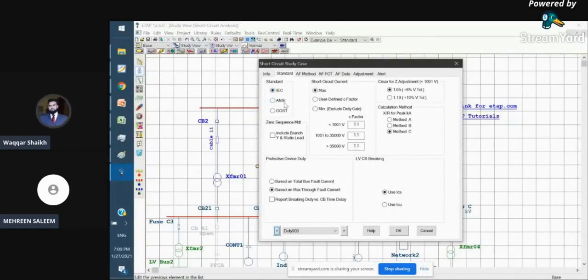There are many options here which will be required from you to select in order to run the simulation. For example, if you are selecting maximum short circuit values, it will give a different set of results. These maximum short circuit values are required when defining the equipment short circuit withstand capability. If you don't fine tune it to maximum and your default option is minimum, you will get lower values and won't be able to size the equipment properly.